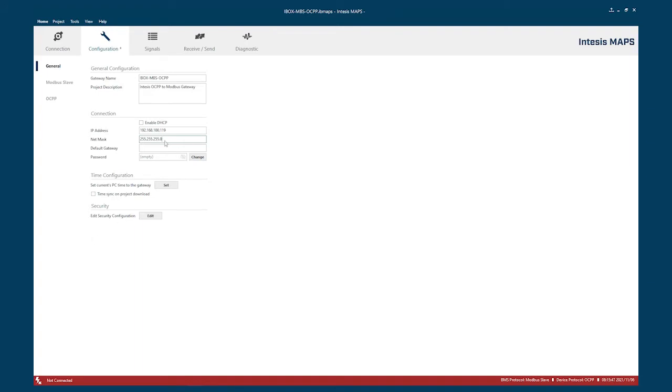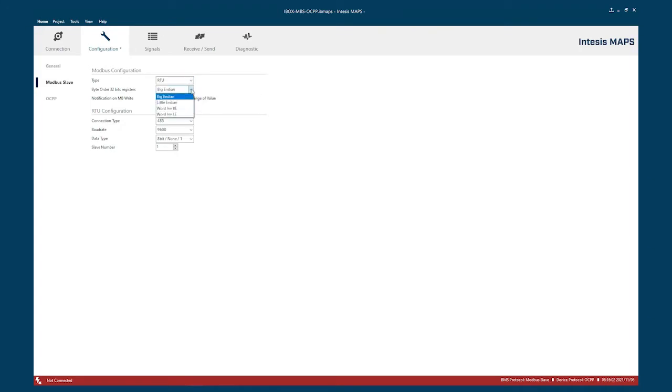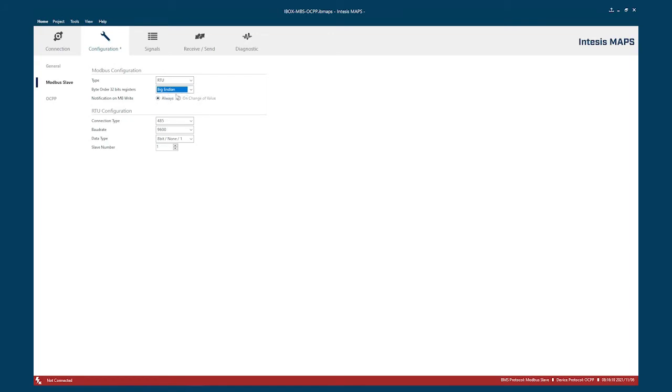This all will be dependent on how you have the setup on your installation. Once you have this with the correct IP address, if you have any Modbus settings, you can here choose between RTU, TCP, or both, how the order is in your registers, big endian, little endian, or default. And if you don't know it, you should find this in your BMS manual or instructions, but you can always go with the default values. That's always a good place to start.